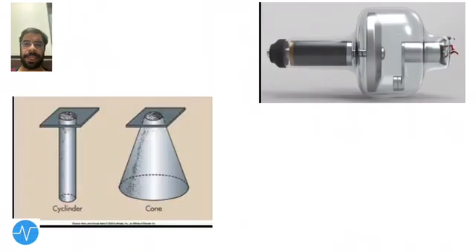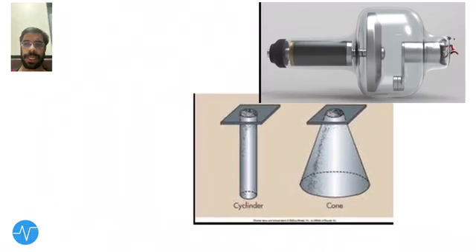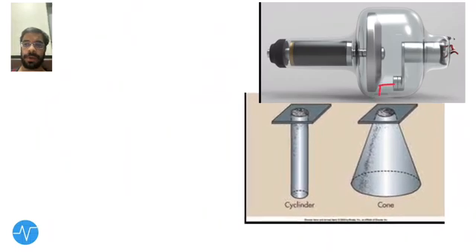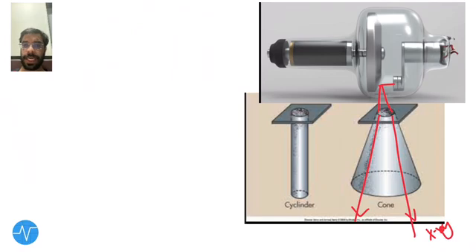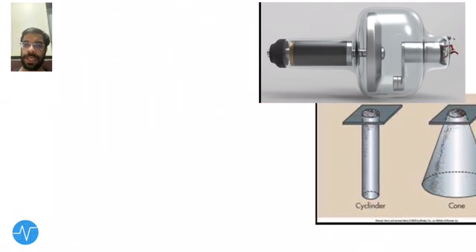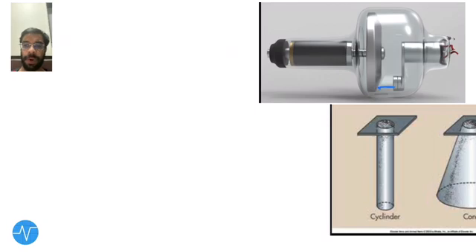Looking at the images: on one side we have the glass tube and on the other the beam restricting device — cone and cylinder. X-rays produced from the glass tube hit the beam restricting device. With the cone, the image is produced in a cone shape. With the cylinder, x-rays pass through and are produced in the shape of the cylinder.